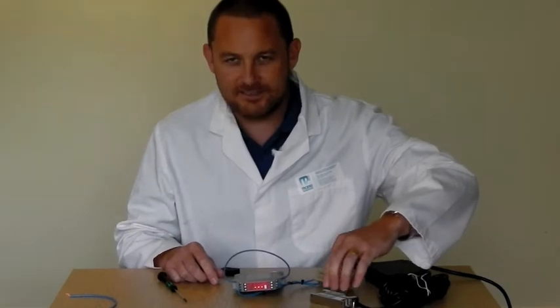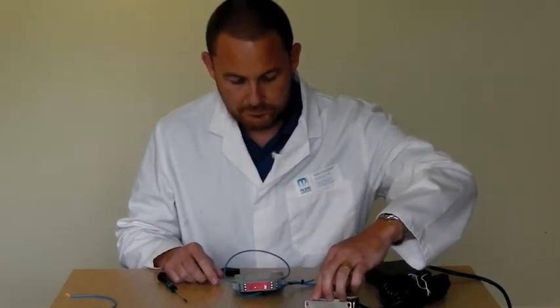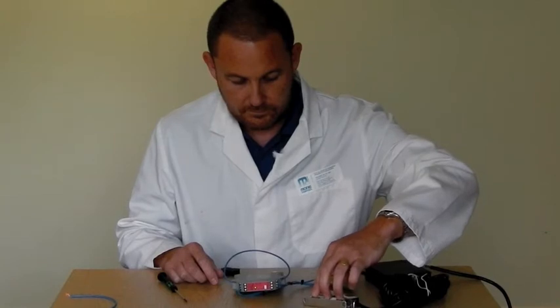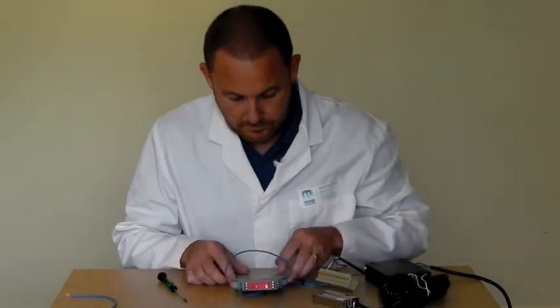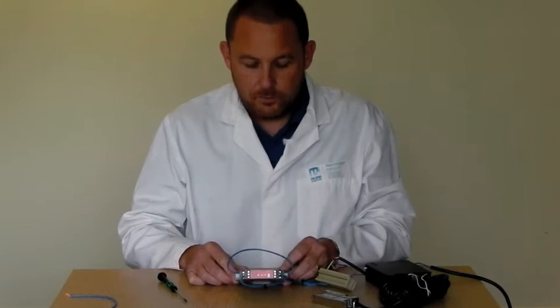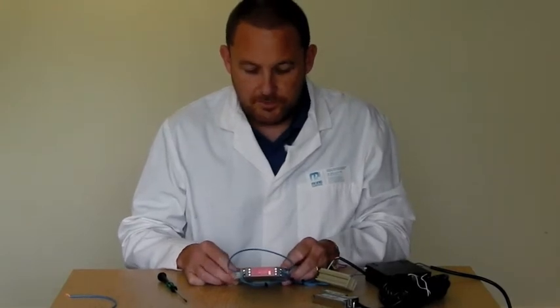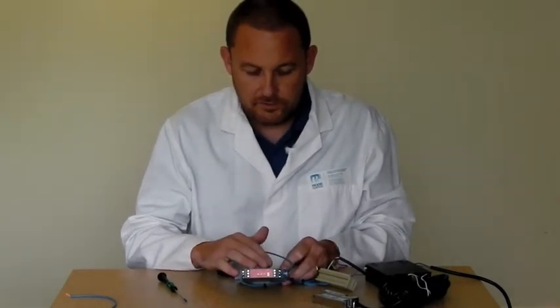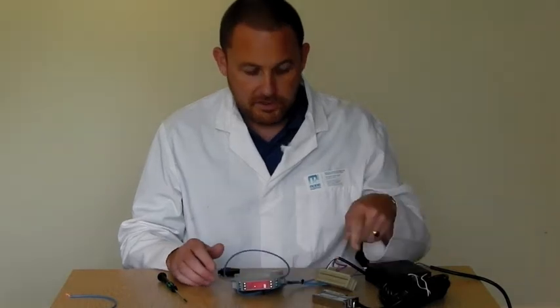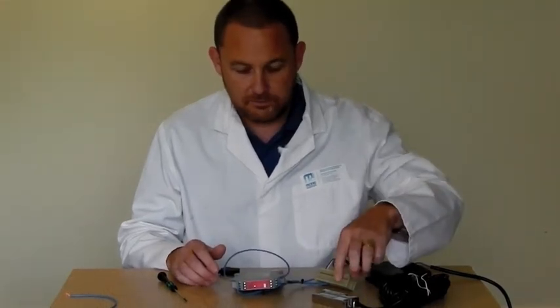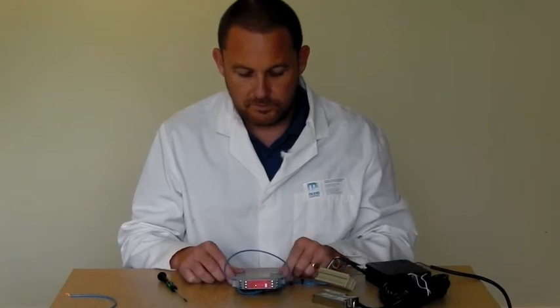So an operator may take the guard off, put it into place, and there we go, one channel was made before the other and the relay's gone into a lockout condition. If we were to pull out the cables, we'd find that both switches are made and we don't know what the problem is.